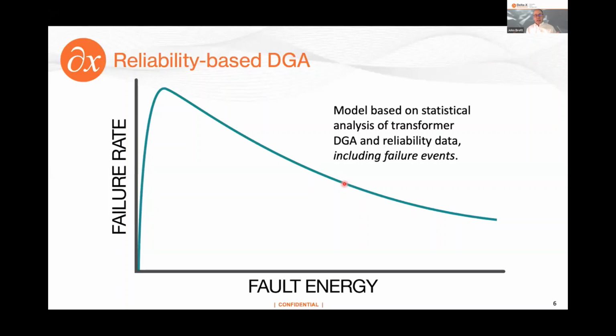But they have a rich gassing history, but they are quite comfortable with that, operating that transformer. They have other things that they need to do, other higher priorities. They still keep an eye on it. But this curve now represents the experiences we're hearing from all those transformer experts in the field.